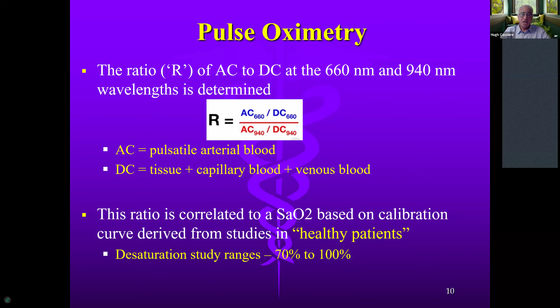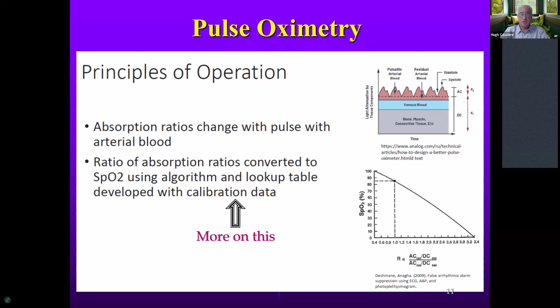It's in healthy subjects. And in these healthy subjects, they do what's known as desaturation studies, where they desaturate patients anywhere from 70% to 100%, and they make this calibration curve. And based upon this calibration curve, you have an R value and now a calibration curve. And then basically what the machine does is the machine looks at what the R is, what the calibration curve is that's programmed into the machine, and it spits out a peripheral O2 sat. A little bit more about this calibration curve on the next slide.